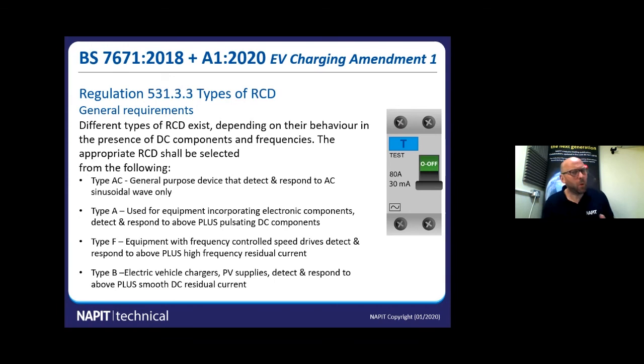Fantastic. So it's really important out there for contractors to look at the different equipment that's on the market, because if you were just to get a standard socket that may be allowed for EV charging, and it didn't have that monitoring built in, you would probably have to use the type B RCD, which would be a lot more expense for the installation.